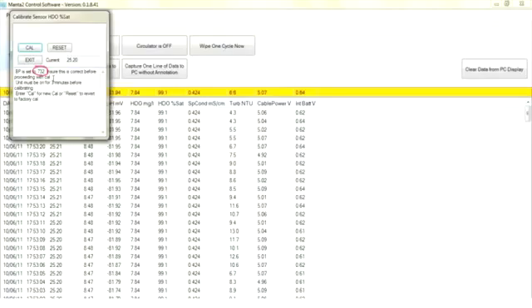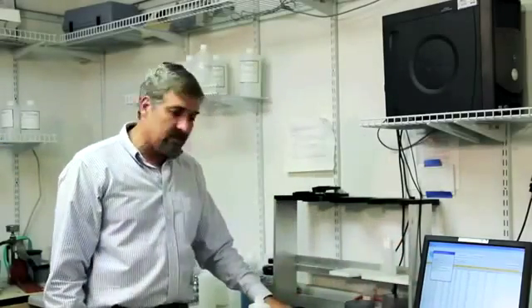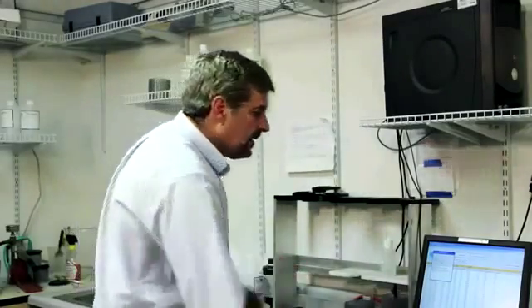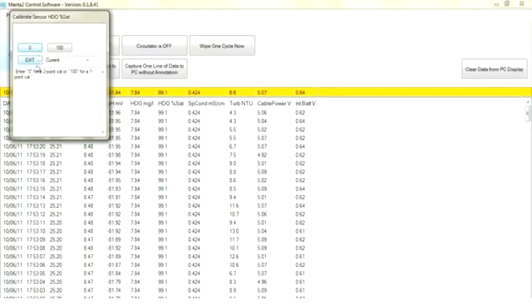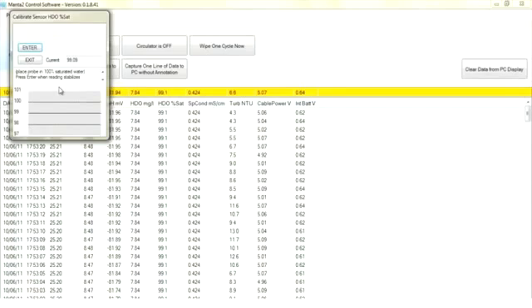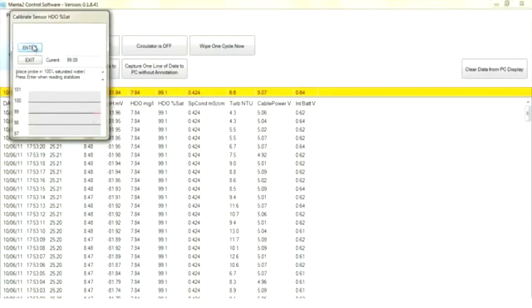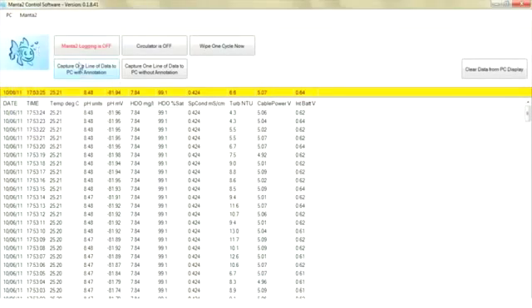I'll go over here to Manta 2. Calibrate. HDO percent sat. That's what we're calibrating. This is now that we've shaken it. It's 100% air saturated water. It says right here BP is set to 732. It's barometric pressure. You always calibrate to your local barometric pressure. I have a barometer sitting right over there. It says 732. I also have one that's built into the multi probe. If you have a low range depth sensor, you can use it for your barometer as well. This is the only sensor where you have to wait on. Whenever you're calibrating optical DO, the HDO, you wait 3 minutes, and then you hit to calibrate. It says enter 0 for a 2 point cal or 100 for a 1 point cal. We're doing a 1 point cal. It's all you need to do. 100. Again I wait for it to stabilize. Showing 100 right now. Enter.